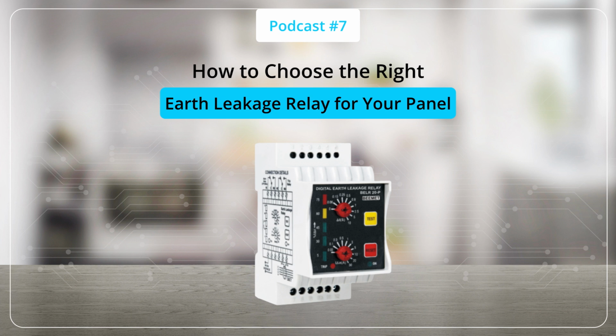The third step is selecting the proper CBCT size. The window size should match the cable bundle that will pass through it. The fourth step is determining the appropriate time delay. Fast tripping is generally preferred when personnel safety is the primary concern. The fifth step is verifying the auxiliary power supply to ensure the relay can operate correctly under site conditions.